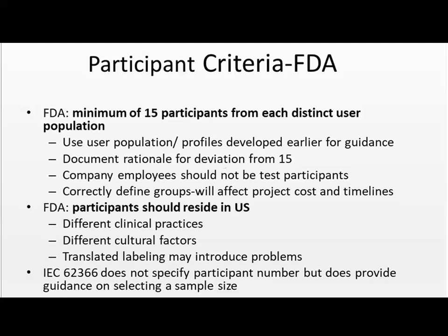As mentioned before, company employees should not be test participants. Also, the FDA has said that participants must reside in the United States, which means the study must be conducted in the United States. The reason is different clinical practices elsewhere, different cultural factors. Even translated labeling could introduce problems because a literal translation may not take into account cultural factors.